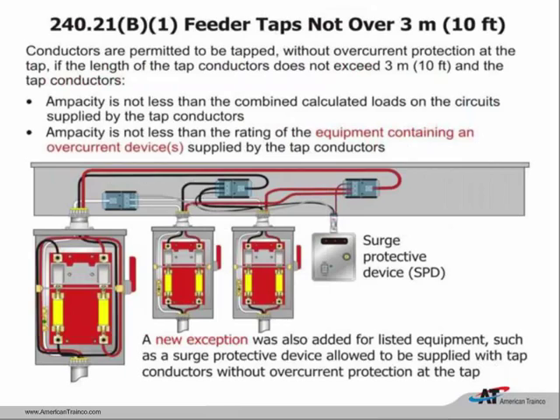Article 240 covers overcurrent protection with three tap rules: the 10-foot, 25-foot, and 75-foot tap rule. If certain conditions are satisfied, equipment can be installed with no overcurrent protection. An exception has now been added for surge-protective devices at the service—they can be tapped off larger conductors with no overcurrent protection. With the advent of electronic equipment entering our facilities, surge-protective devices are extremely important. Two code cycles ago, the transient voltage surge suppressor and the surge-protective device were combined into one article. These devices help against transients, dips, and swells to protect electronic equipment.